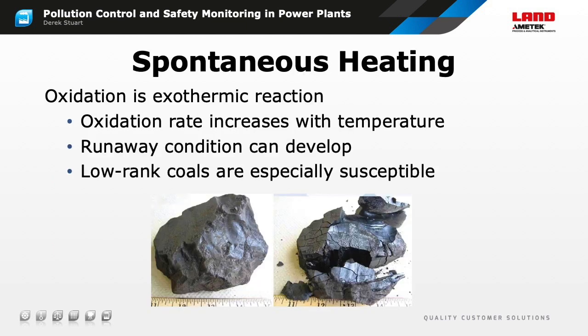As coal ages, it tends to oxidize and to crumble. This increases the surface area, and so the rate of oxidation increases. Oxidation is an exothermic reaction, heating the fuel and further increasing the oxidation rate, so that a runaway condition can develop, eventually causing spontaneous combustion when the coal catches fire. As well as the obvious safety concerns, spontaneous heating and combustion can result in the loss of the purchased coal, which is no longer available for use in the boiler.